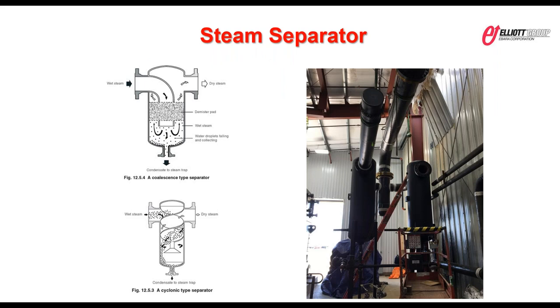Yeah, I mentioned steam separators. There's really two types that we see that are very common. A coalescing type separator, where you have some sort of filter media or baffles in there that help separate the moisture from the dry steam. And then a cyclone type, which causes kind of like a high speed rotating flow. Those larger, more dense wet particles then drop out of the bottom and can be drained from a condensate trap.